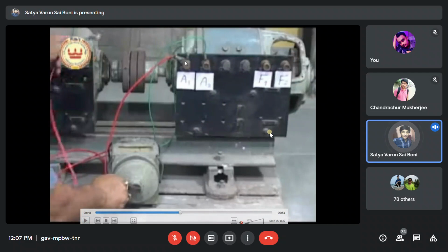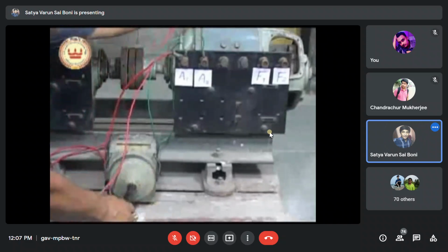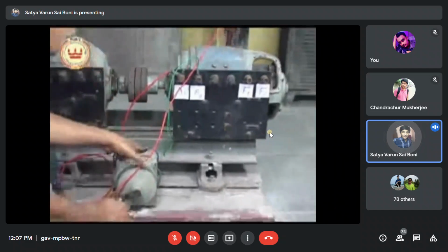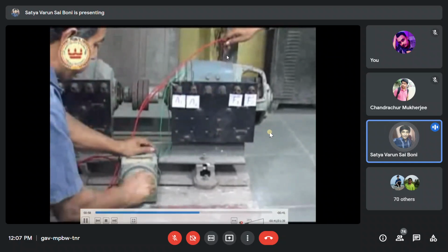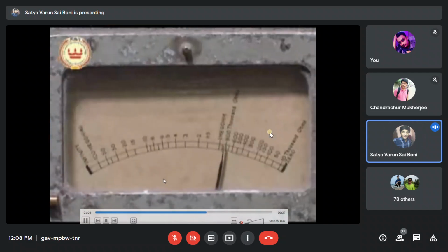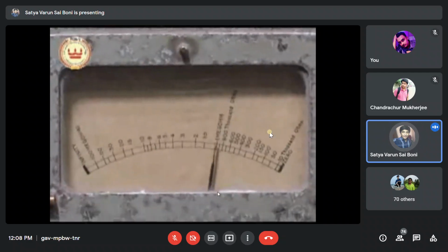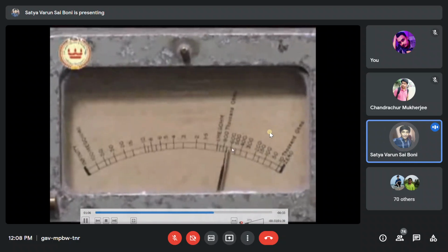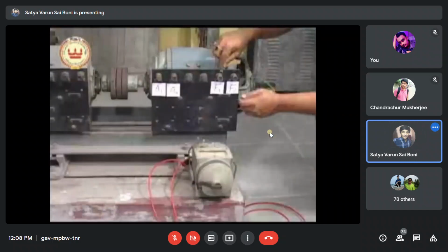See, he shorted the lines. You can see here, he shorted both the lines, and from one of the knobs he gave it to the megger. And the other point he will ask, because this experiment can't be done by one person, because one person should hold that thing above. You can see one person holding that thing on the yoke. He is just moving it, handling it slowly, and it comes like this. Means it will show the measurement, which is the insulation resistance.